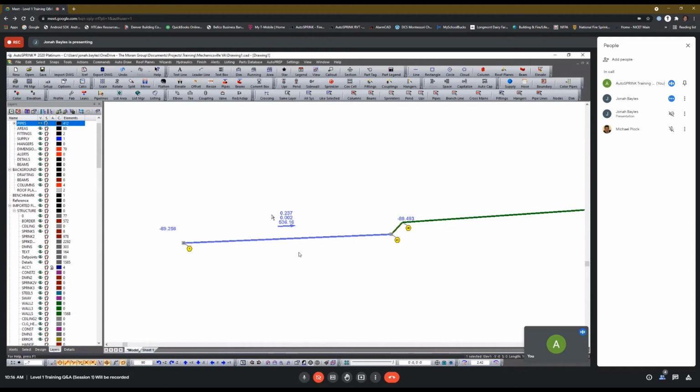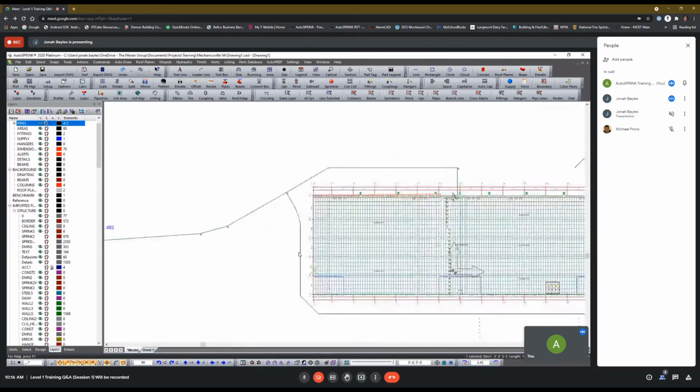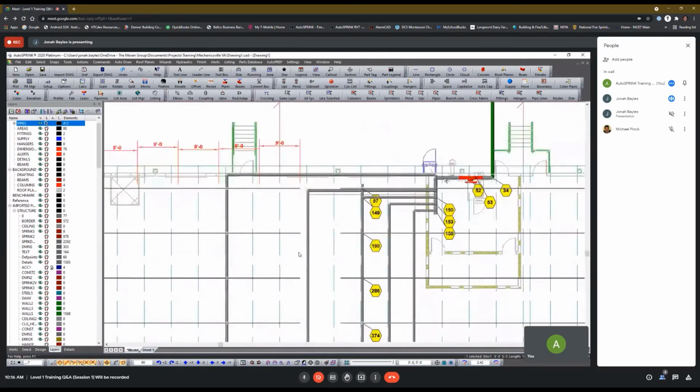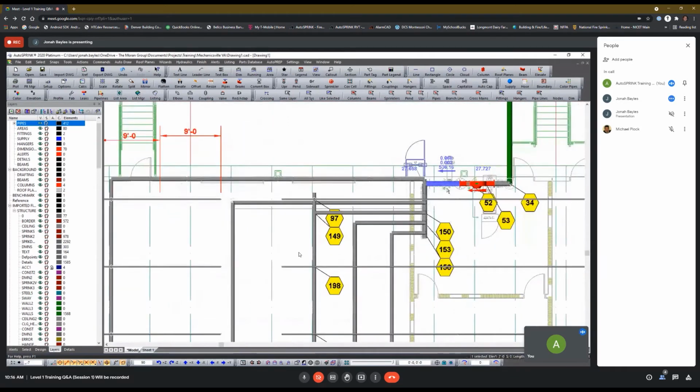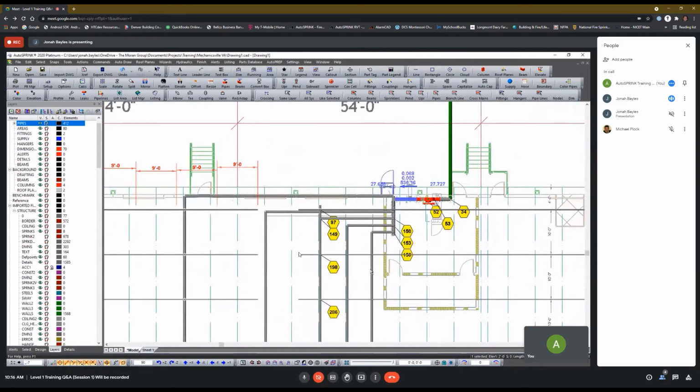As far as your negative required pressure, that's normal to see when we have a fire pump, and the fire pump is producing all of the pressure needed for the system demand. Okay. So if I go over here, it should be positive. Yes, exactly. That makes a lot more sense.